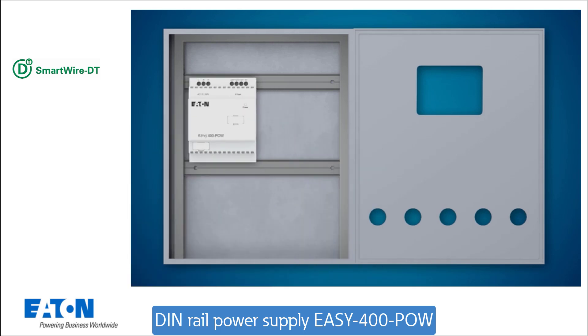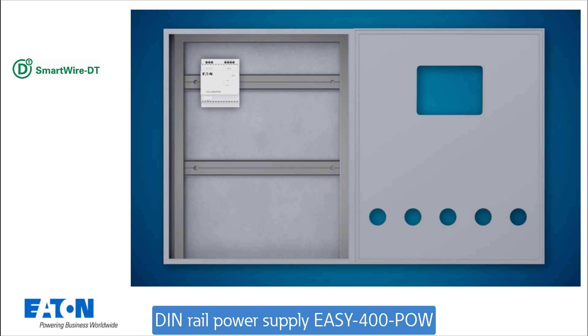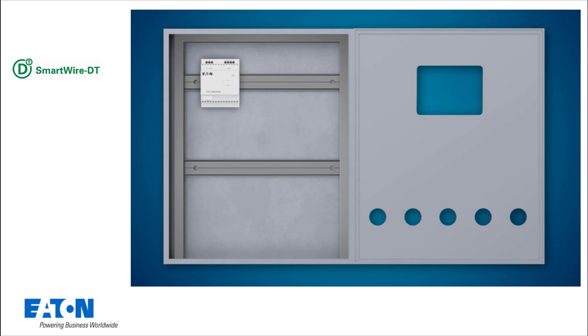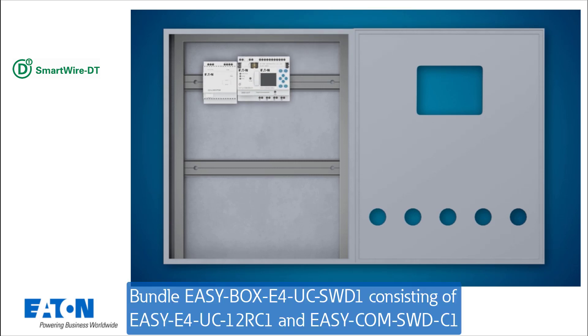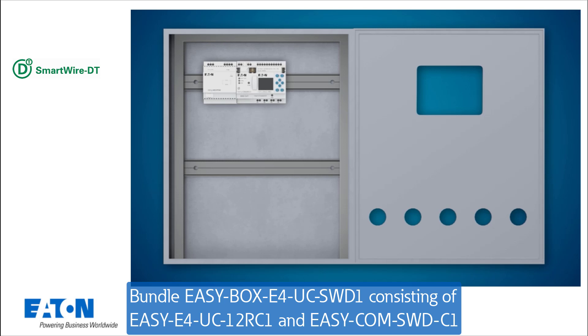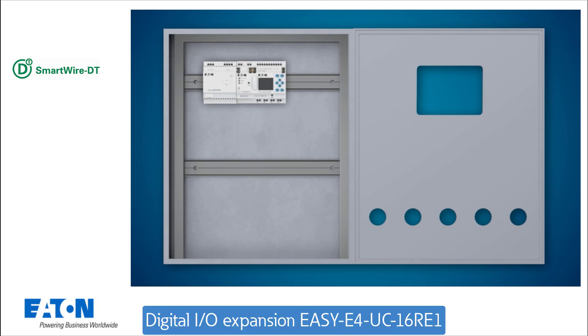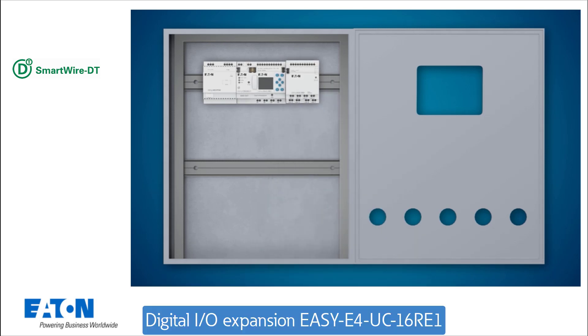The 24V power supply is provided in the control cabinet via a DIN rail power supply unit. The Easy SmartWire DT bundle with the EasyE4 Basic Unit in UC version and the SmartWire DT communication module is inserted. For additional relay outputs, the UC expansion with 8 relay outputs is placed on the right-hand side of the EasyE4.